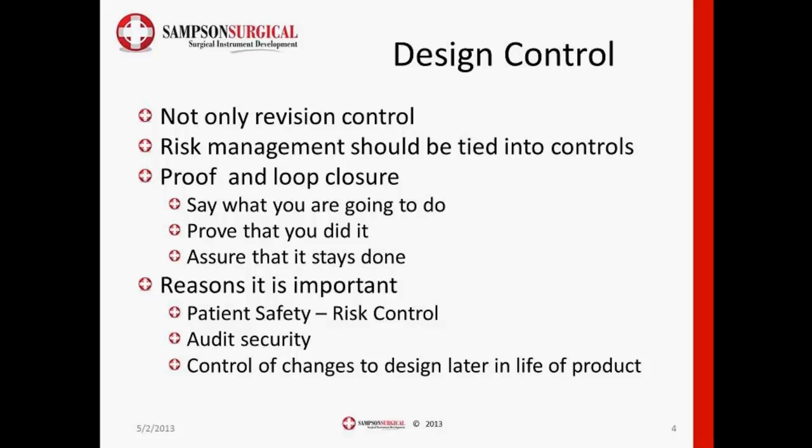And you can imagine that in an FDA audit, they come in, and one of the favorite things to do is to start with your CAPA system, your corrective and preventative action system, determine what problem you have identified in your company that's wrong, and then drill down. They end up someplace in the system, and you don't always know where that place is going to be, so you'd like to have a design control and risk management system that allows you to take wherever they end up and then back it out either up to the patient harm, or into your verification testing for the design validation and verification. So just 3 good reasons to do that.